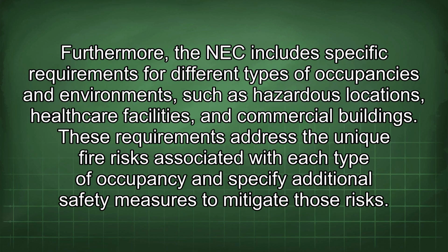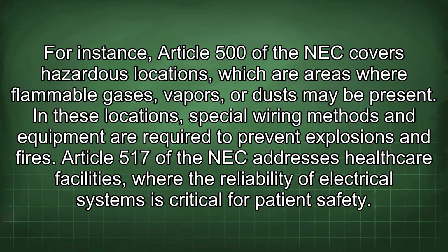Furthermore, the NEC includes specific requirements for different types of occupancies and environments, such as hazardous locations, healthcare facilities, and commercial buildings. These requirements address the unique fire risks associated with each type of occupancy and specify additional safety measures to mitigate those risks. For instance, Article 500 of the NEC covers hazardous locations, which are areas where flammable gases, vapors, or dust may be present. In these locations, special wiring methods and equipment are required to prevent explosions and fires.